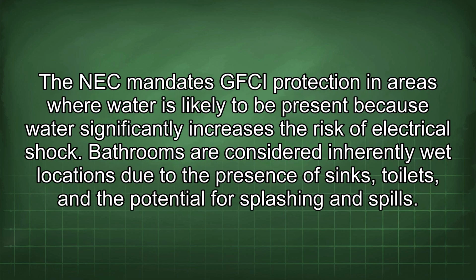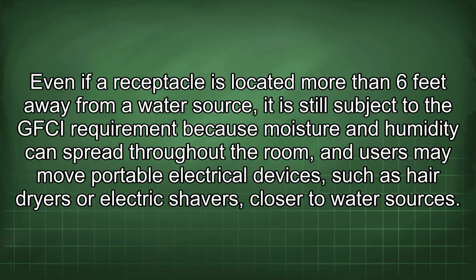The NEC mandates GFCI protection in areas where water is likely to be present because water significantly increases the risk of electrical shock. Bathrooms are considered inherently wet locations due to the presence of sinks, toilets, and the potential for splashing and spills. Even if a receptacle is located more than 6 feet away from a water source, it is still subject to the GFCI requirement because moisture and humidity can spread throughout the room, and users may move portable electrical devices such as hair dryers or electric shavers closer to water sources.